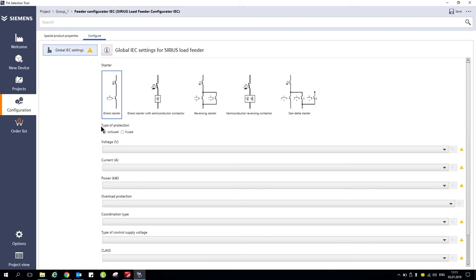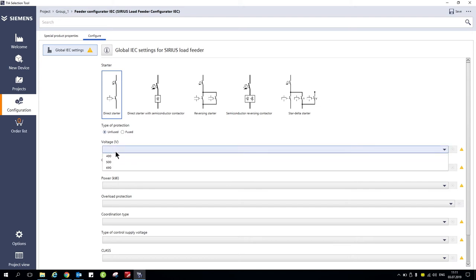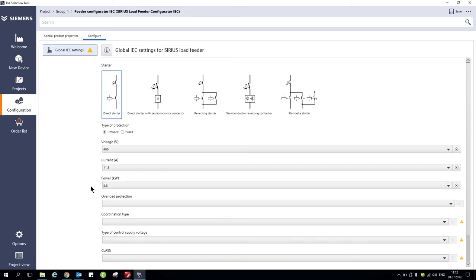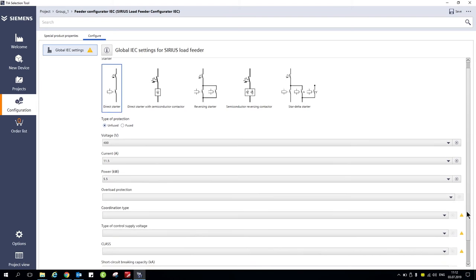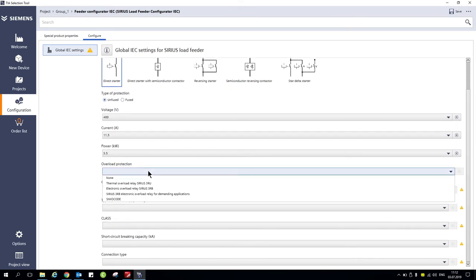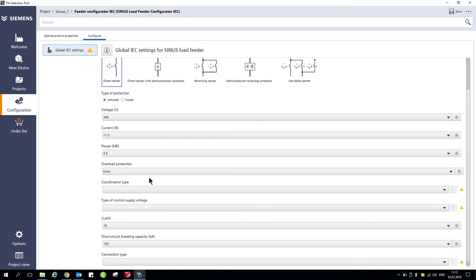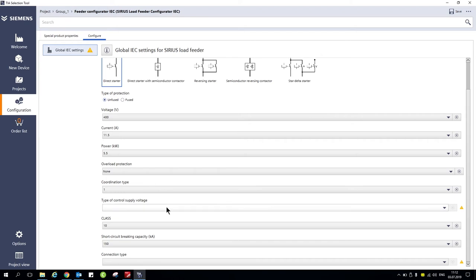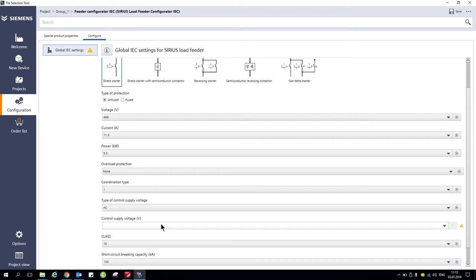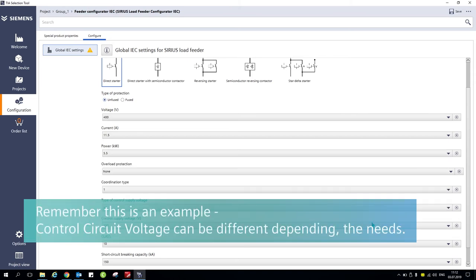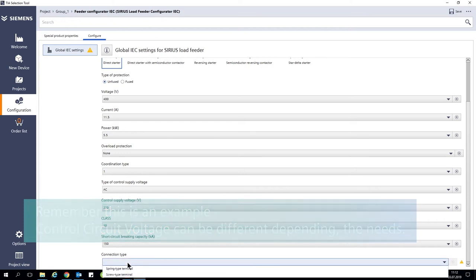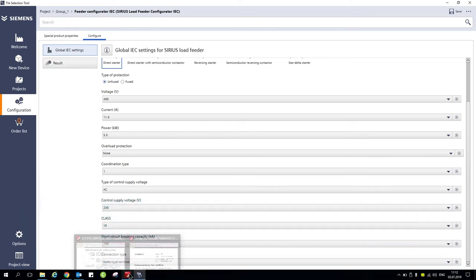Click Configure and let's select a direct starter — an unfused direct starter with a voltage of 400 volts. We go for a power of 5.5kW. As you can see, the current is automatically displayed. Then, scrolling down, we select overload protection as none. Coordination type 1 or 2 — we go for type 1 in this example. Type of control supply: we go for AC at 230 volts. Now we need to select the connection type, where we can find spring type or screw type — we go for screw type. Then, automatically, the result tab pops up.